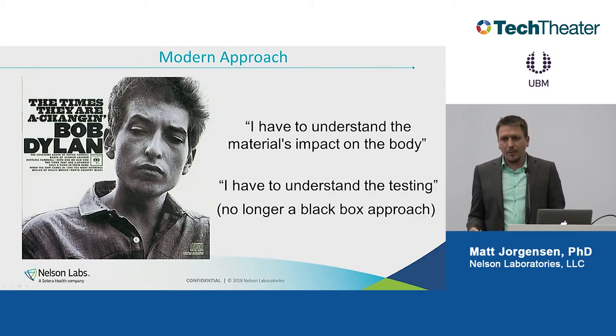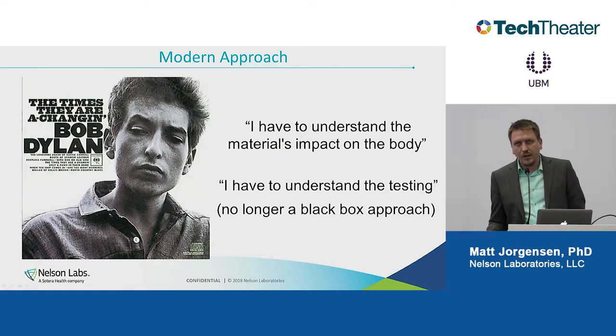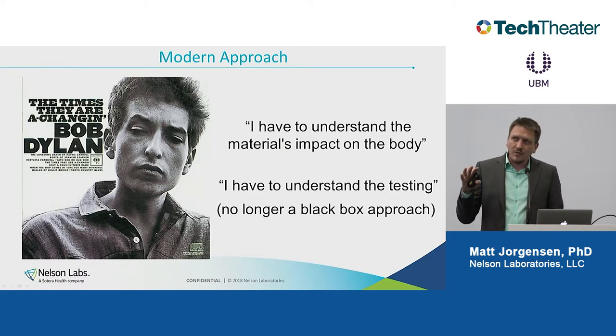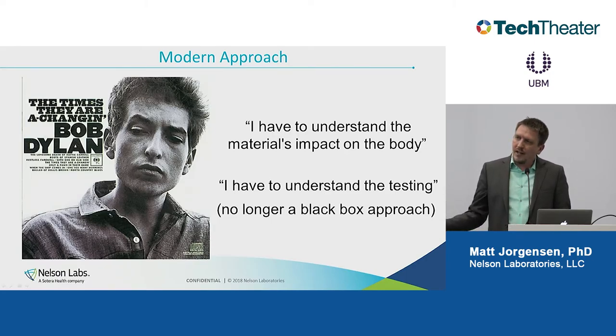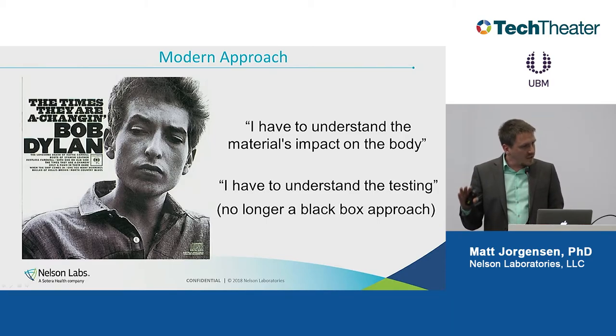So now we're in a place where there's a lot larger burden on the manufacturers in terms of what needs to be understood. There needs to be an expert in materials that really understands those materials and how they interact with the body. So there's a higher burden there, but the overall testing burden can be a whole lot less. Because if you really understand your device and the materials, then using a risk-based approach to the evaluation, you can reduce the burden quite a lot that way.